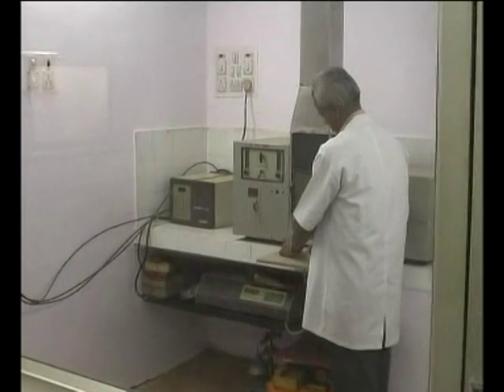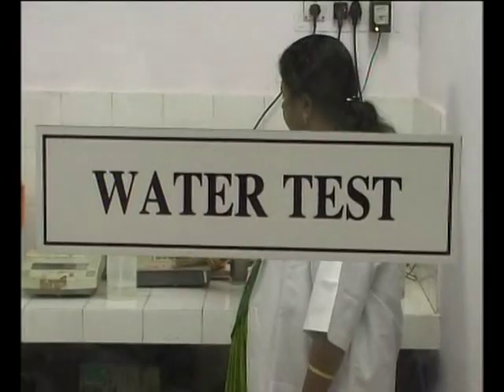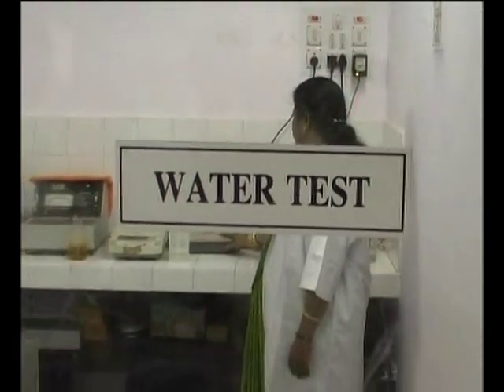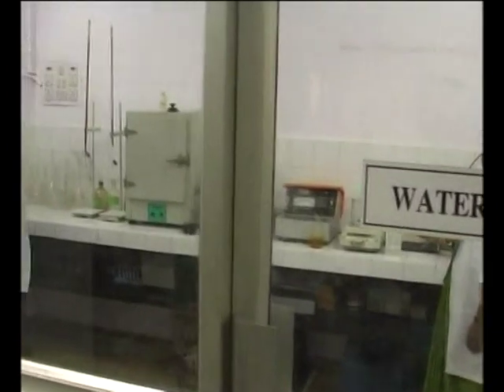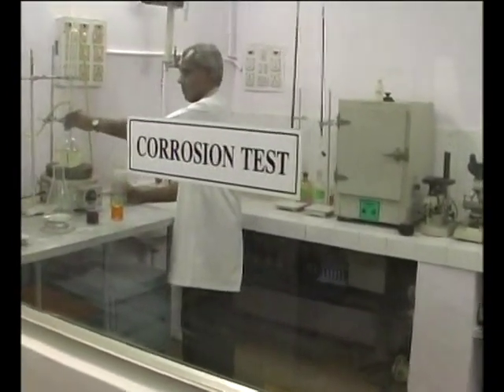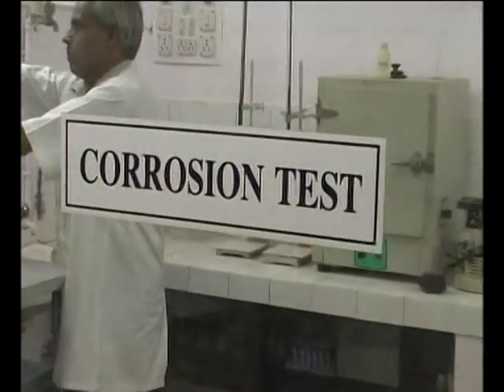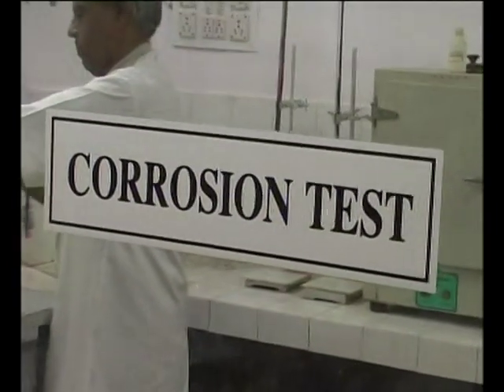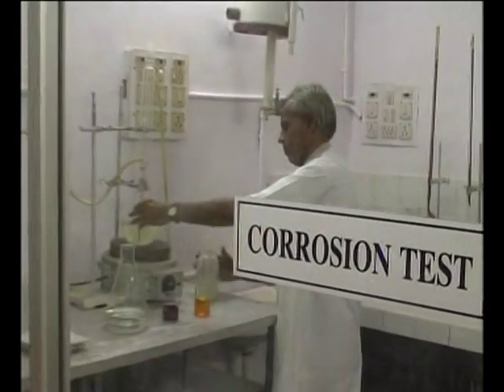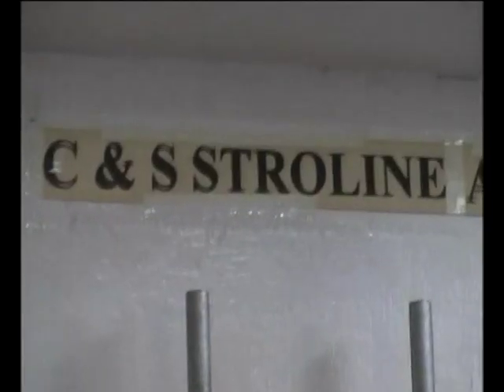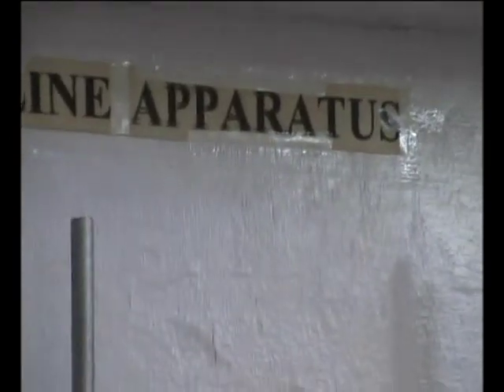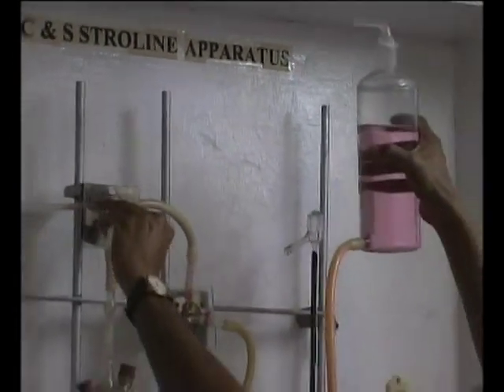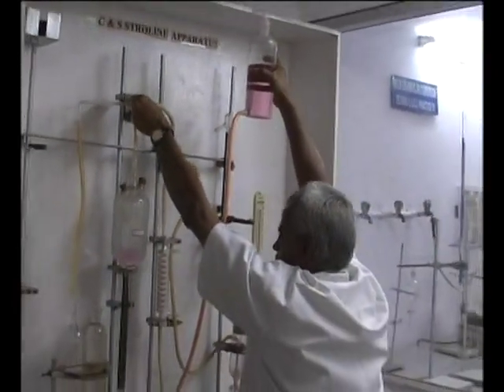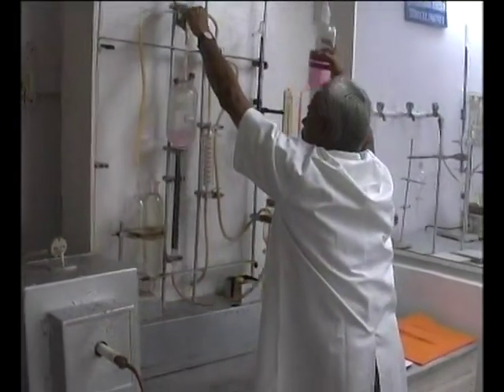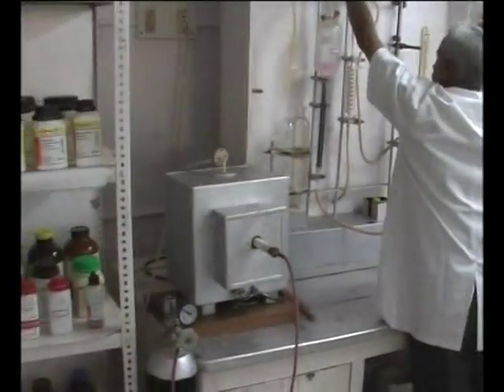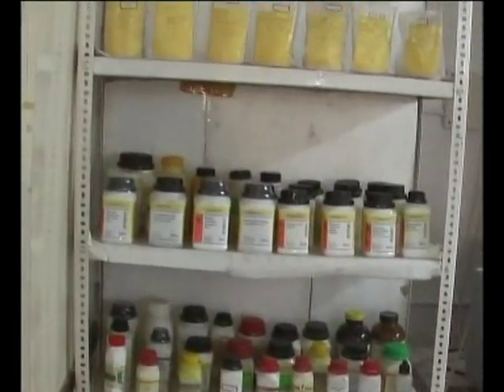In water samples, total hardness, TDS, pH, electrical conductivity, chloride, sulfate and magnesium can be tested. Corrosion test can be done here for valves and pumps. We have a C and S analyzer apparatus to test the percentage of carbon and sulphur in steel. This instrument is calibrated by NPL standards. E-Merck standard chemicals are used in this process.